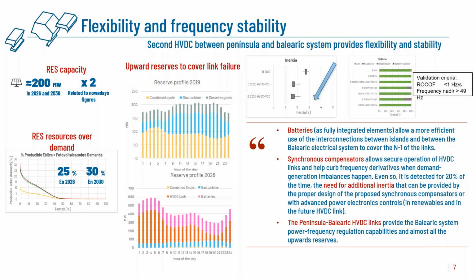So the commissioning of the second Peninsula Balearic HVDC link, together with the batteries and the associated synchronous compensators, offers the system the entire reserve to ramp up in emergency situations to cover the failure of an HVDC pole or an AC undersea link between islands. That means that batteries, as fully integrated elements, can only provide these ramp-up reserves in this N-1 or failure situation of one of the links, HVDC or AC links. So the foreseen increase of renewable capacity in this system, on the other side, means, as you can see in this figure, a very high decrease of system inertia.